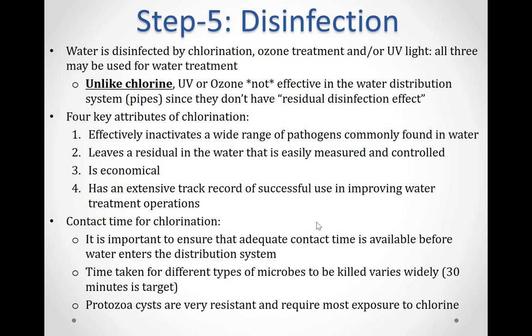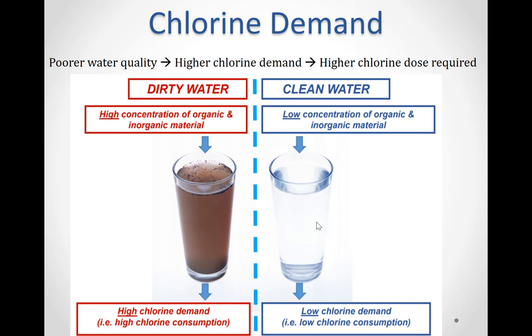It is very important to ensure adequate contact time for chlorination before water enters the distribution system. The time taken for different types of microbes to be killed or inactivated varies widely, and typically 30 minutes is the target. Protozoa cysts are very resistant and require the most exposure to chlorine. Dirty water contains high concentrations of organic and inorganic material, thus dirty water will have higher chlorine demand and require a higher chlorine dosage. Clean water, on the other hand, has low chlorine demand.